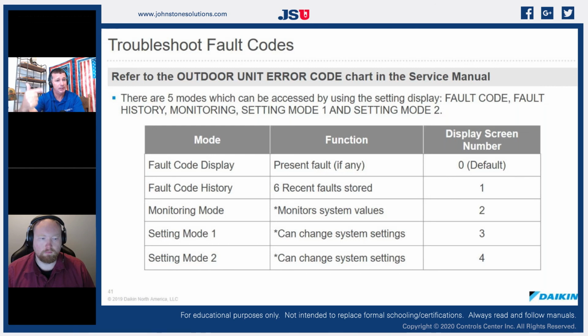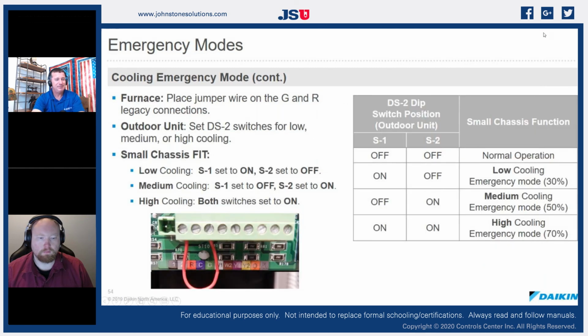We can go into the lower layer, the monitoring mode, and look at all of those readings. Every one of those temperature sensors and pressure transducers, I can look them up in the menus and see what they're actually reading. Because if I get a diagnostic code for an outdoor air temperature sensor, I want to go to the outdoor unit, go into my monitor mode and see what it's reading. If it's a 95-degree day and it's showing 50 degrees, I might have a bad sensor. But I need to go unplug it, check the resistance on it and verify that. So not a difficult thing to do.